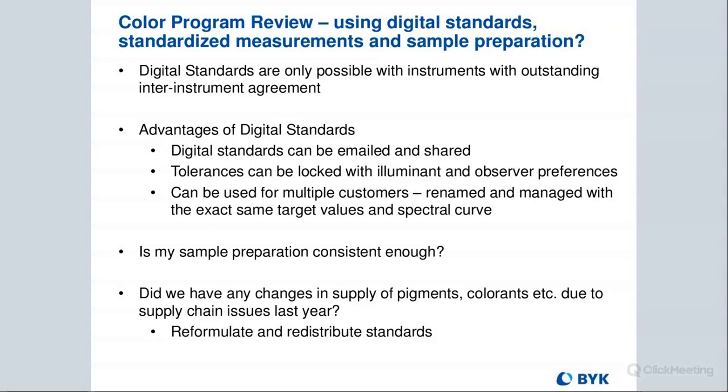The other thing that's important when we're making a digital standard is that we always measure the same. So this is important because, again, like I talked about earlier, the BYK-Mac is a directional illumination. So if we measure the standards differently every time, maybe with the instrument perpendicular to the panel and then horizontal to the panel, we're going to get different numbers.